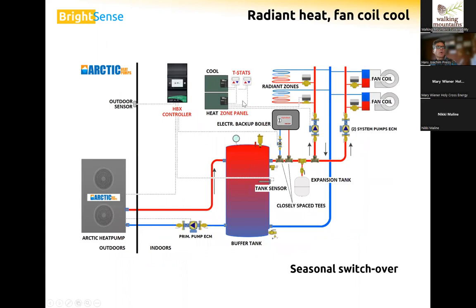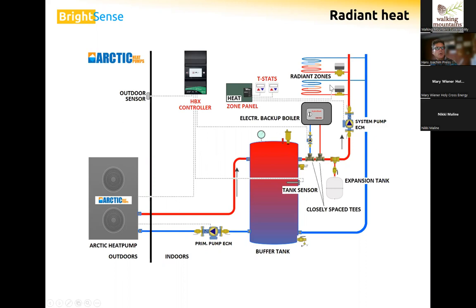If we wanted to do cooling, we could certainly do radiant cooling also. Radiant cooling is a new buzzword that can certainly be implemented with the heat pump. There are a few things to keep in mind. It requires new construction because it requires certain things to be implemented. You need to have a radiant cooling controller with a dew point sensor. You don't want to have any condensation anywhere, not on any piping in the walls or floors. Those all need to be insulated. And you certainly don't want to have any condensation on any floor surfaces.